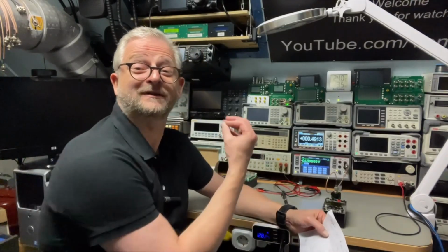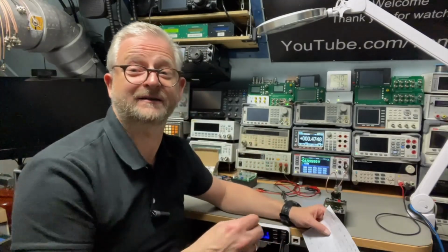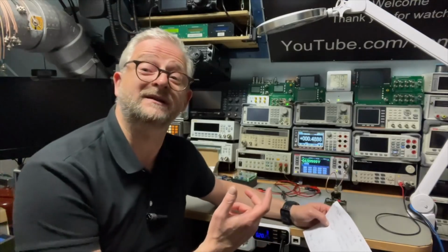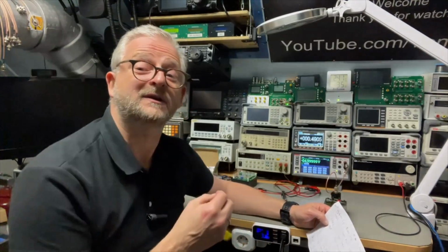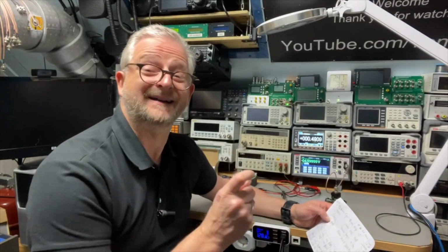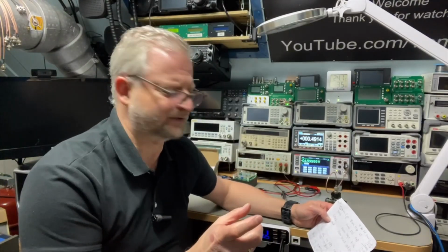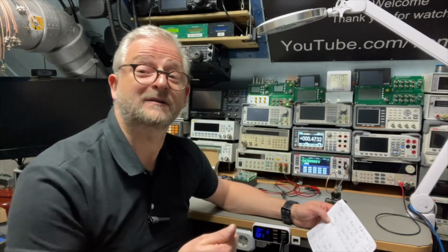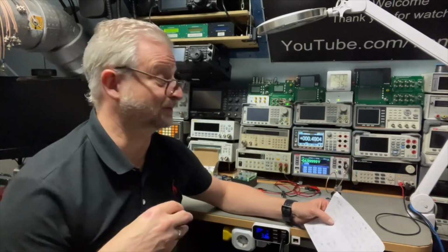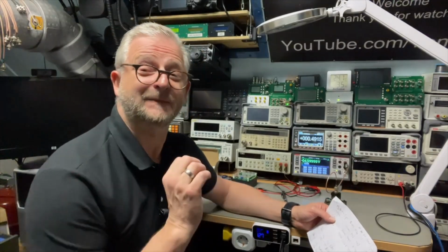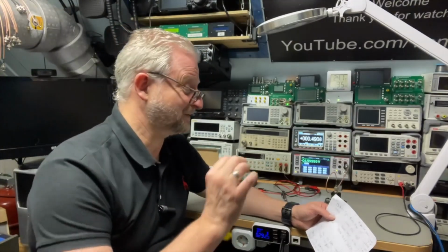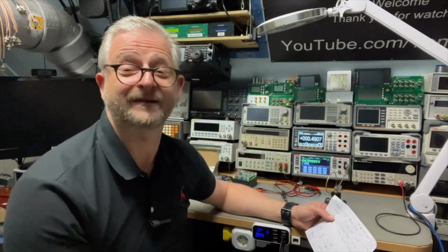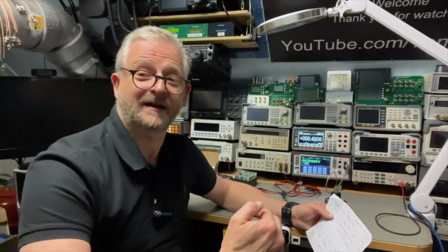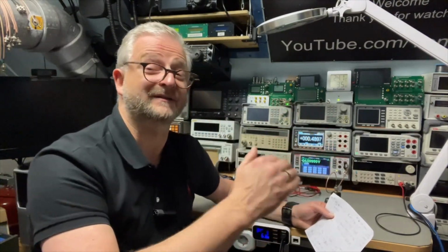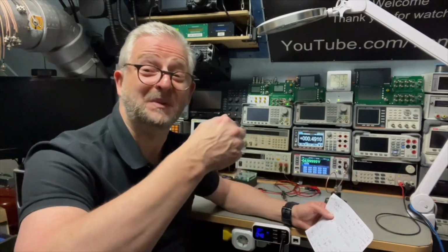When we look at the cleanliness, we could already see graphically that the Chinese calibrator was a bit more noisy, even though it was still within the specifications. Then we saw that the LBO2 was very nice, but we see there that the peak was about 300 microvolts, and the deviation was about 90. Well, clearly the shootout was about the last two, the DMMcheckPlus and the WRYtech. The WRYtech was just a little bit better. If we look at the peak, it was like 25 for the DMMcheckPlus and like 22 on the WRYtech, and the standard deviation for the DMMcheckPlus was just above 3 microvolts, which is pretty good. But for the WRYtech it was even below 3 microvolts.